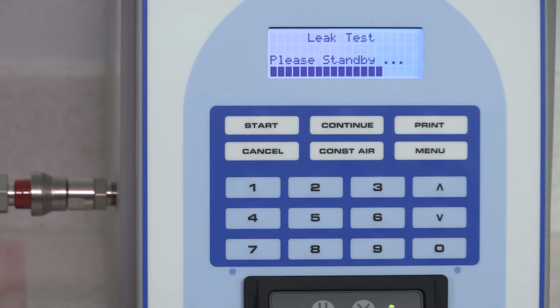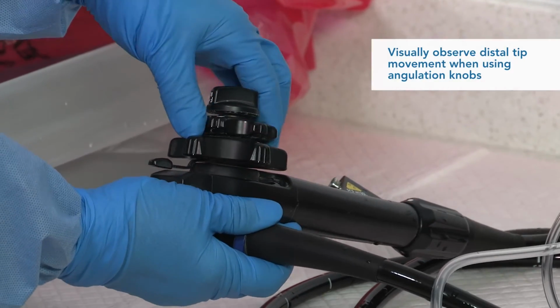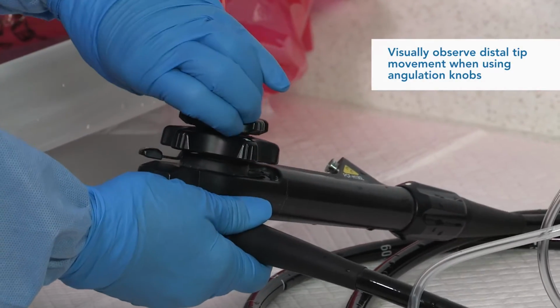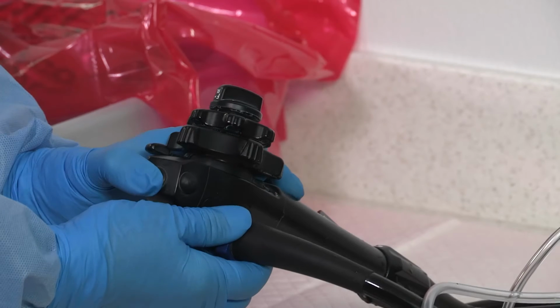The leak test automatically begins and displays Leak Test, Please Stand By. You will hear the air pump cycling on and off during the leak test. After a preset time period, an audible tone sounds and the unit displays text on the screen that prompts the operator to turn all the endoscope's angulation knobs and to press all the camera switches.